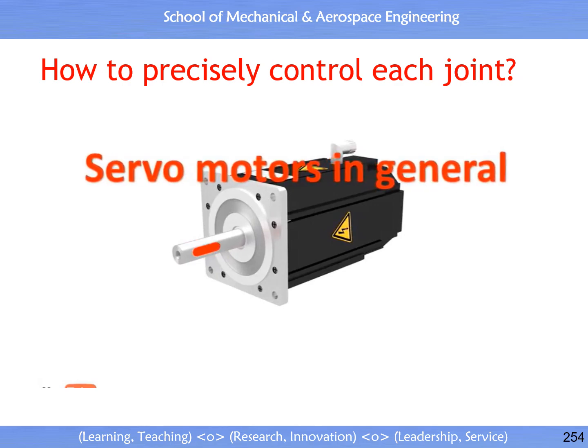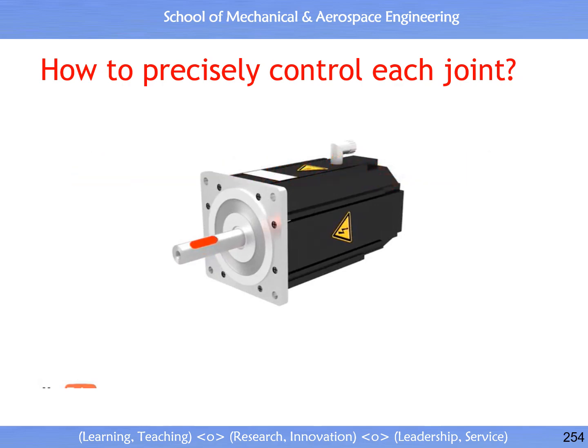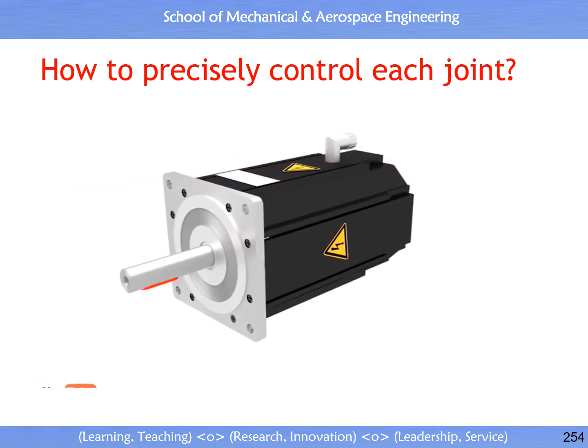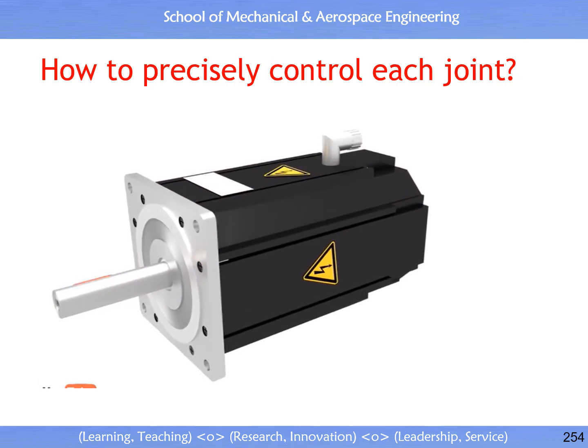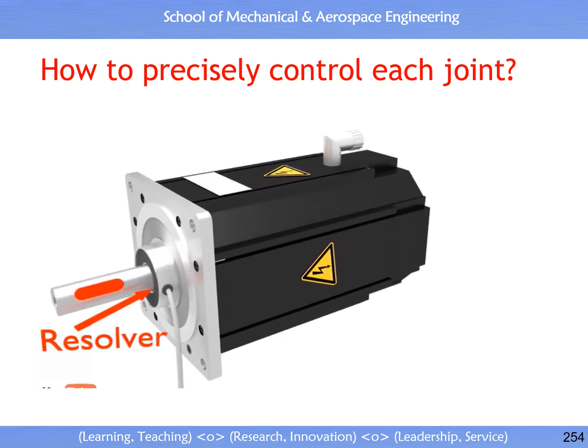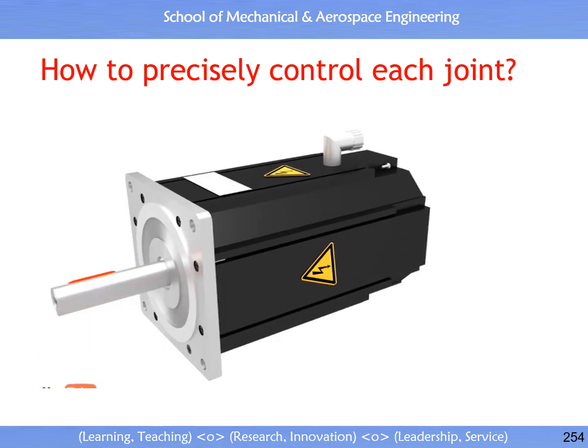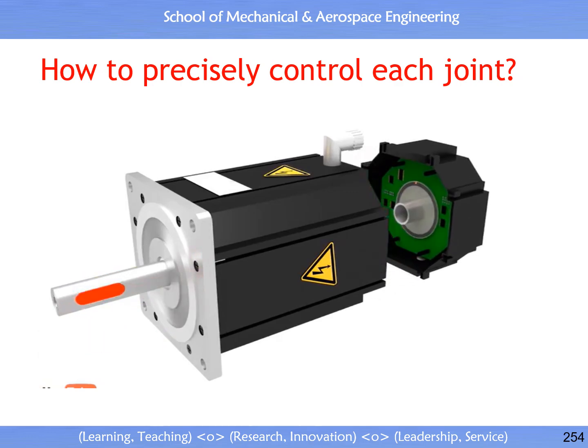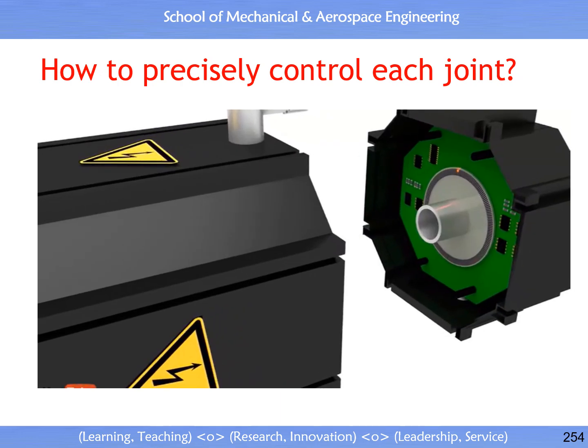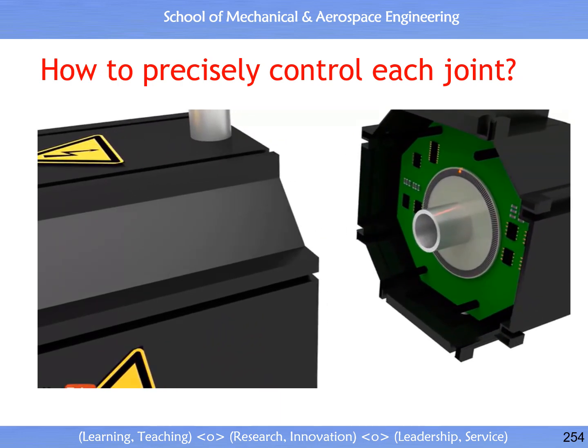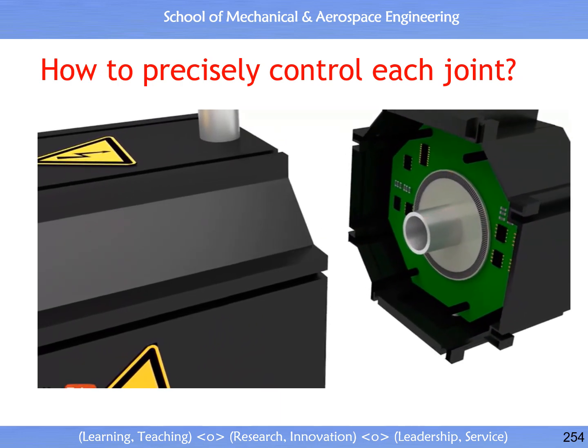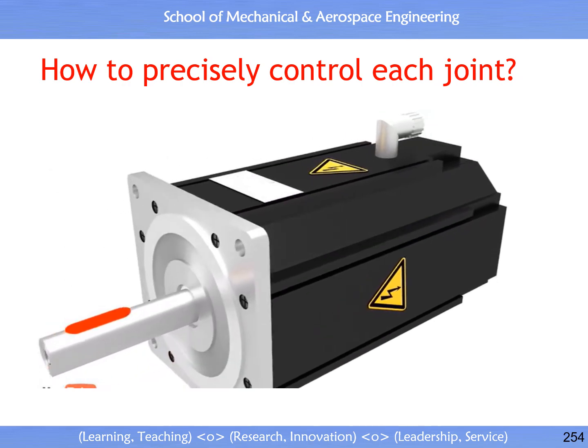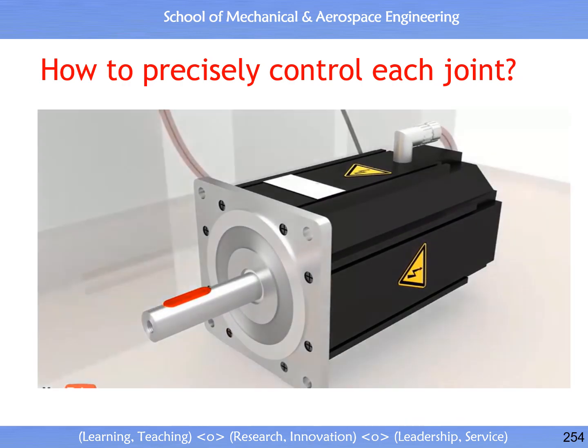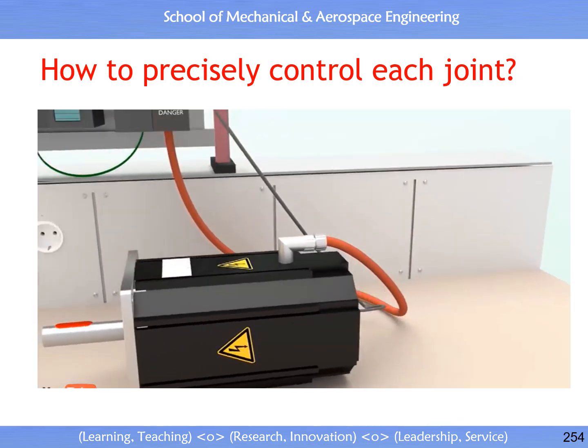The servo motor is a part of a servo drive, whether brushless DC motor, synchronous, or a robust asynchronous motor. But one thing in common is the detection of the rotor position by a sensor. This can be a resolver or an encoder. In this case, you see an incremental encoder. This sensor device gives feedback to a controller to keep, for example, the rotational speed or torque constant, or to reach the target position as fast as possible.